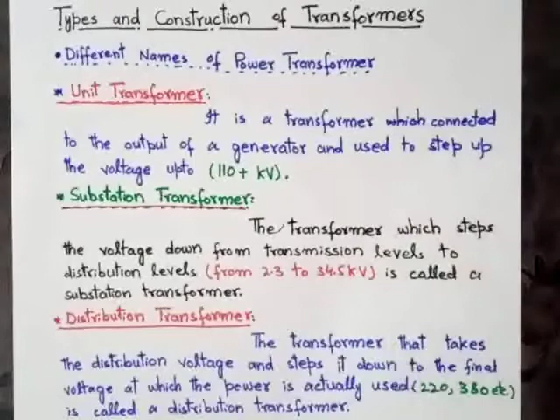The second type of power transformer is the substation transformer. Substation transformers are the transformers which step the voltages down from transmission levels to distribution levels, that is from 110 plus kilovolt to 2.3 to 34.5 kilovolt. That is, the unit transformer is basically used to step up the voltages and the substation transformer is basically used to step down the voltages. This is the difference between the unit transformer and the substation transformer.